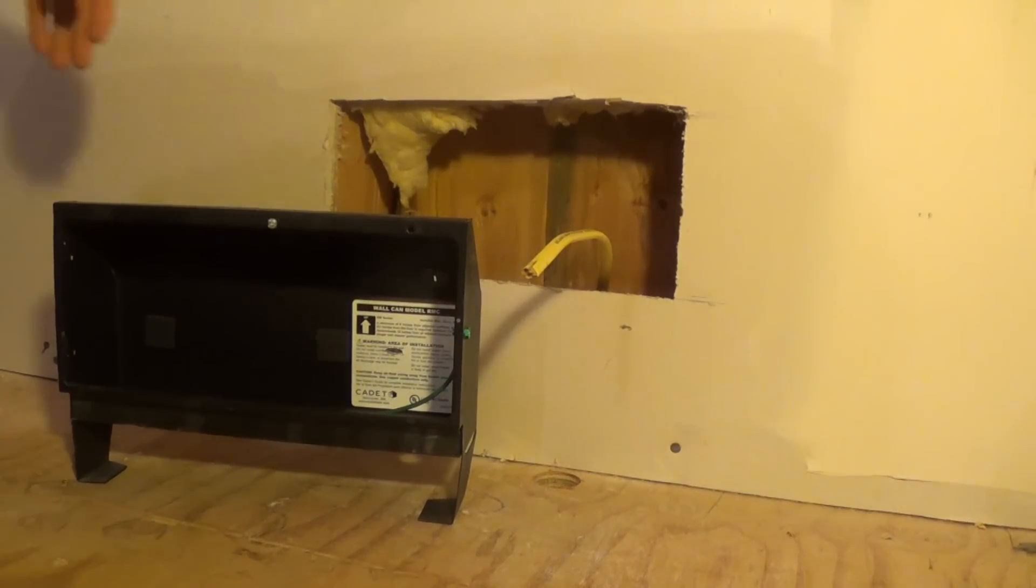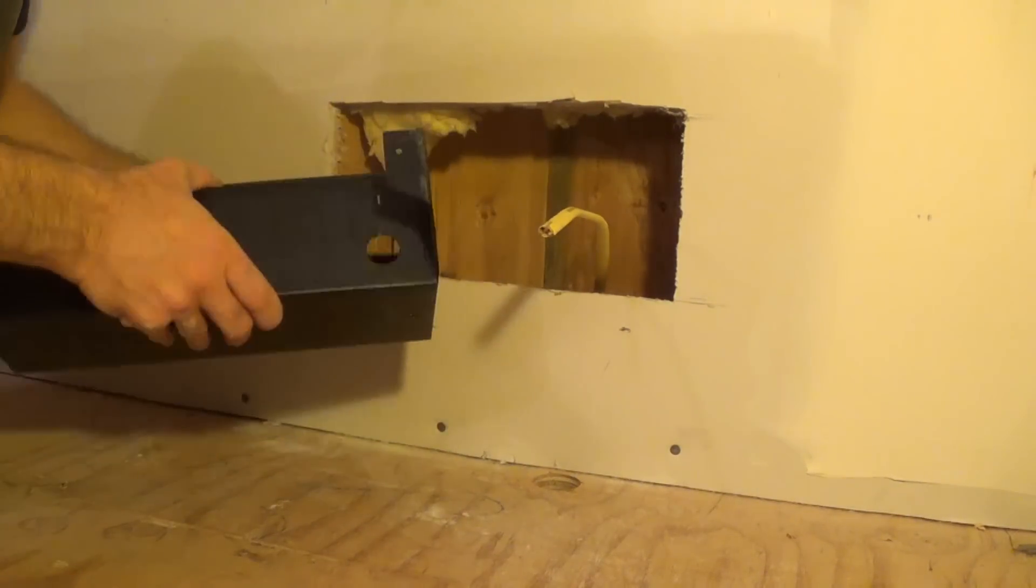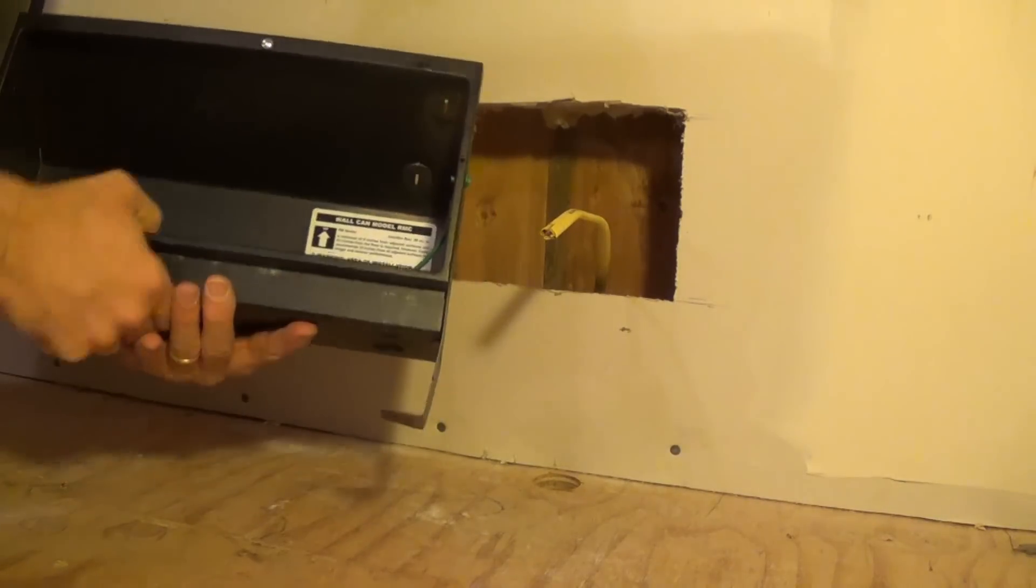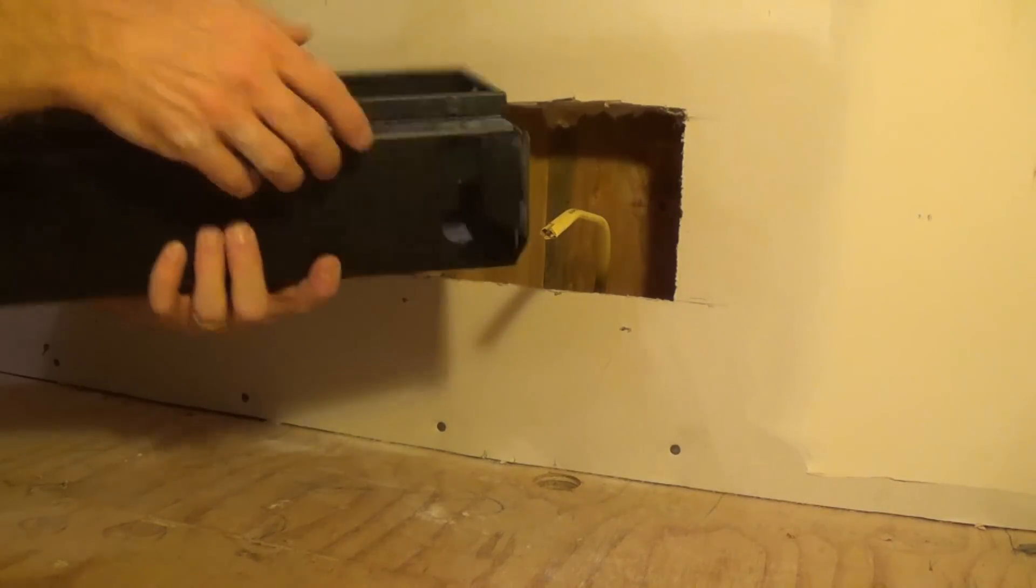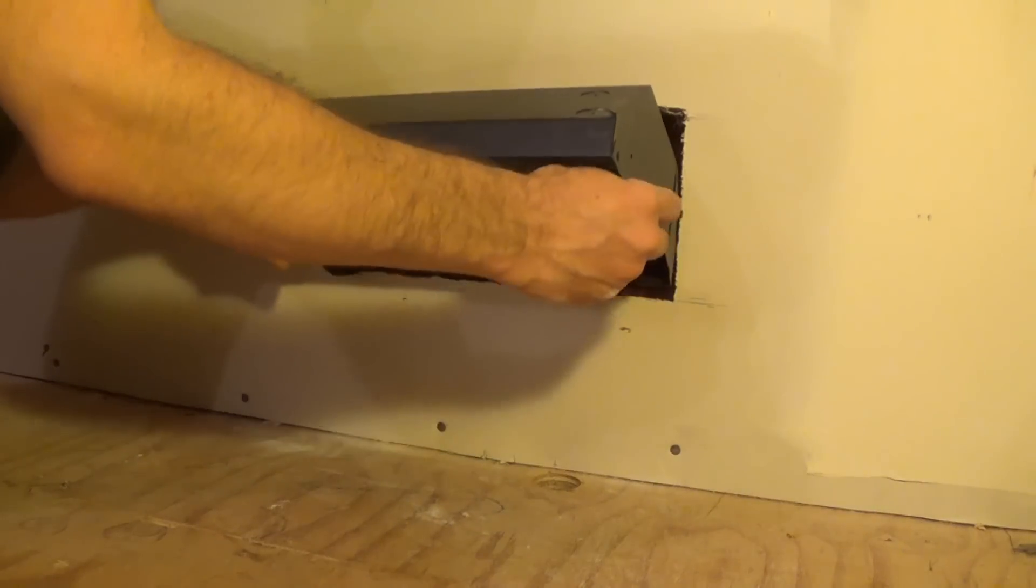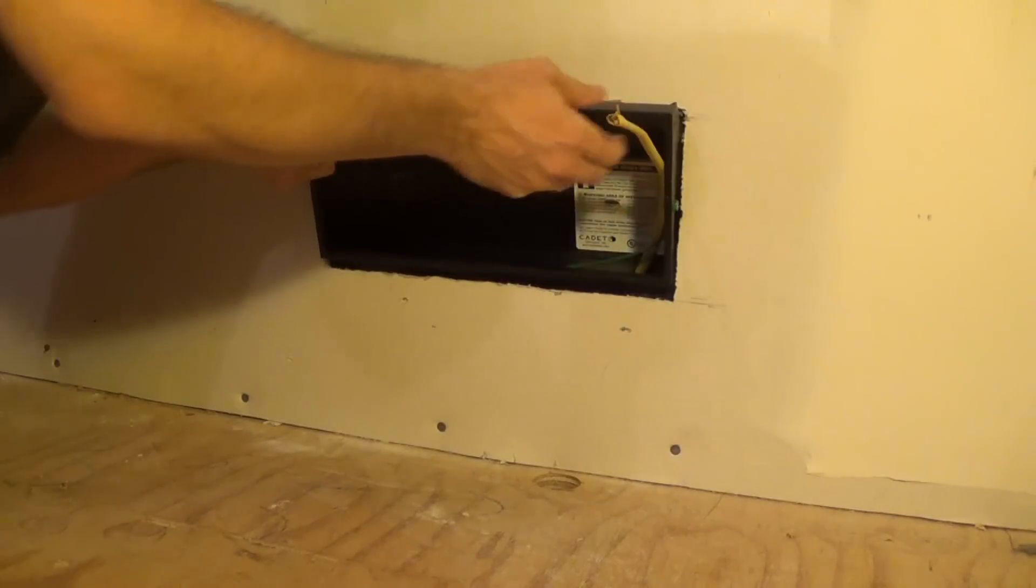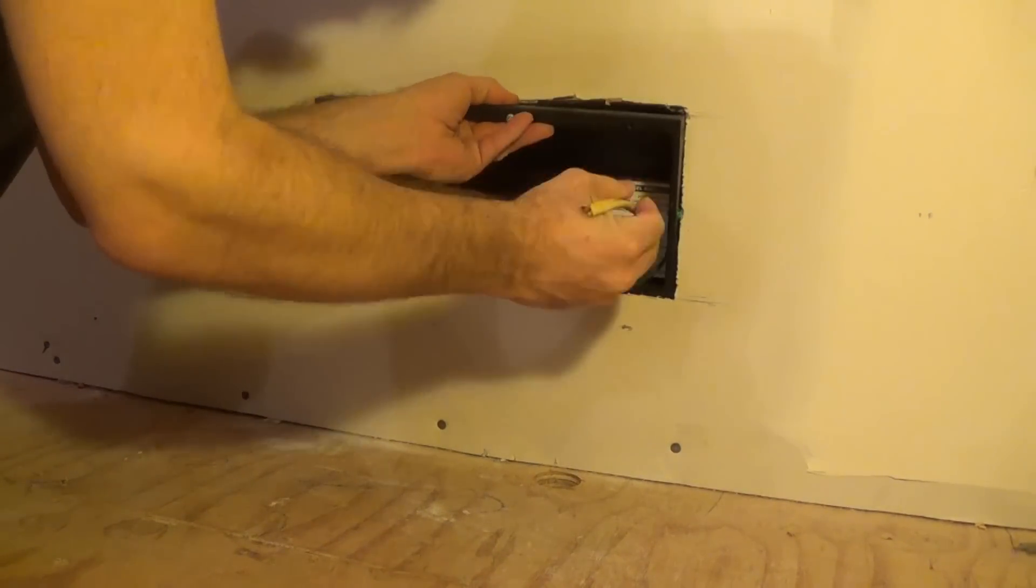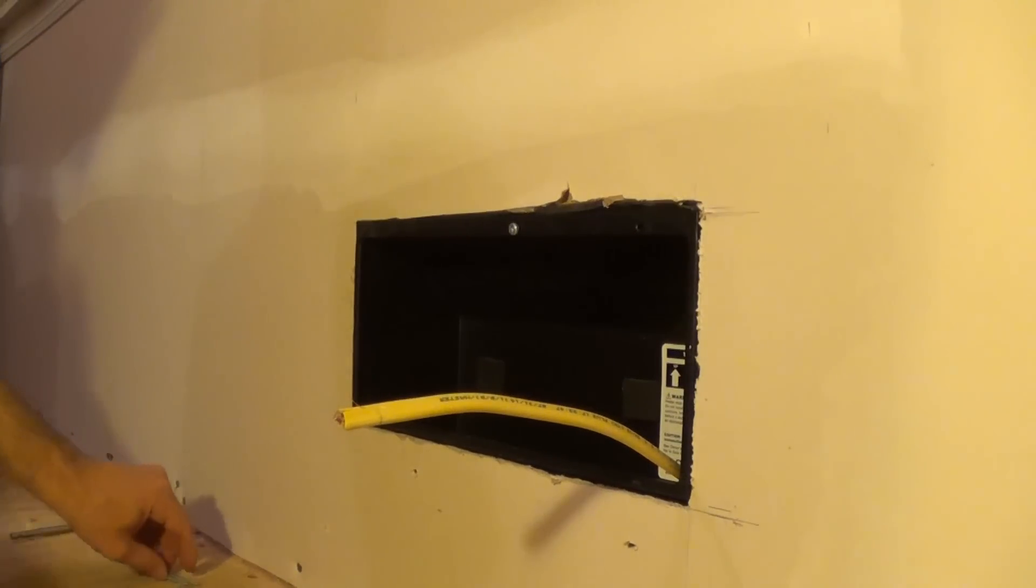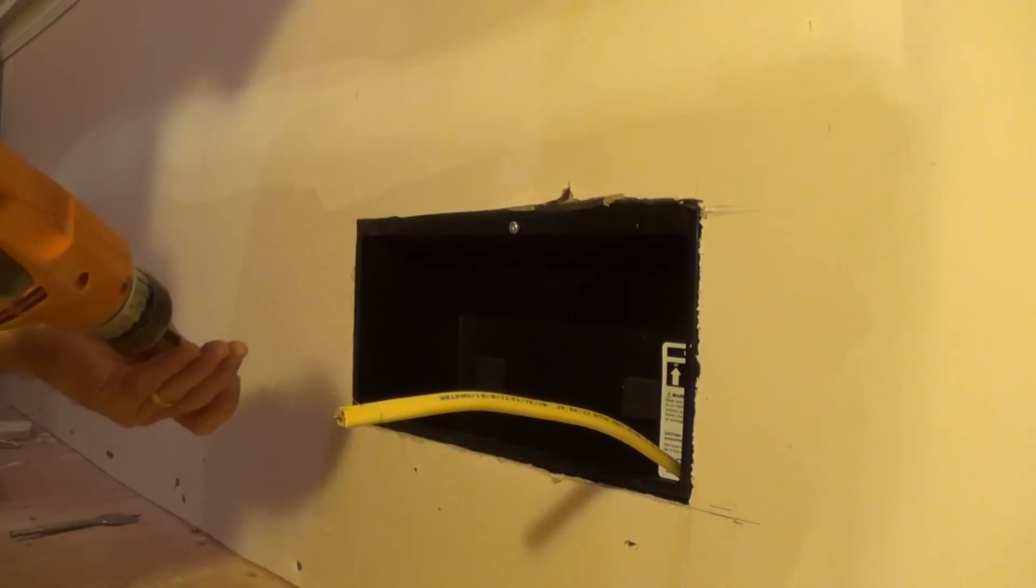Okay, so I got the power line supply in here - it's a 240-volt line, 20-amp. I popped off one of the access holes here and I'm just going to feed this in and kind of fit it in. Now I'll secure the box to the stud that's on the side.